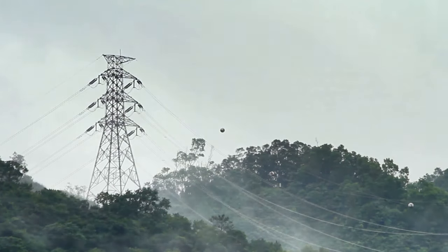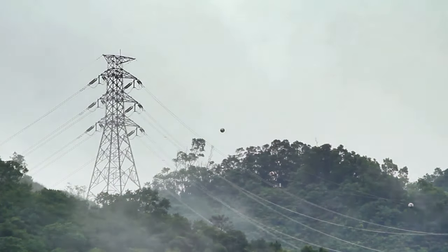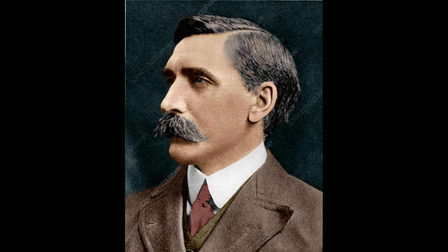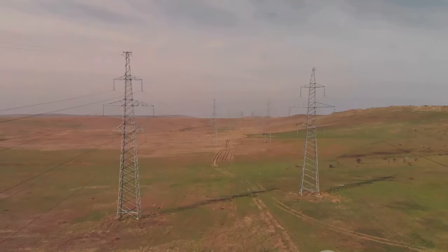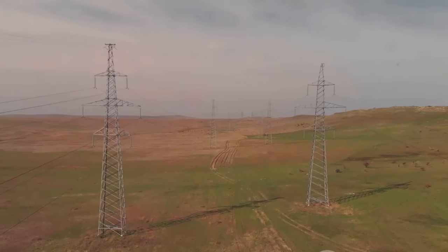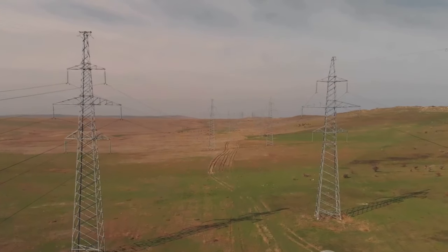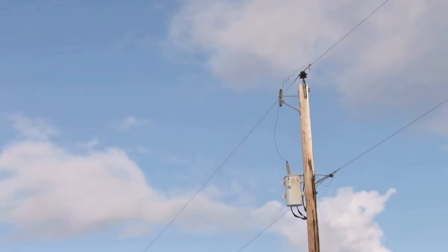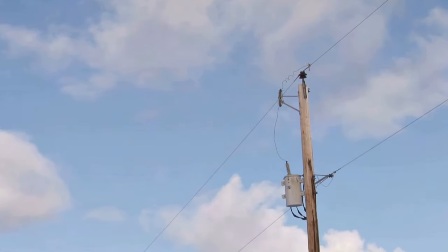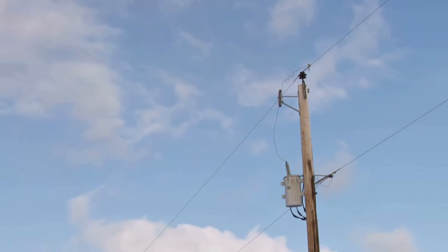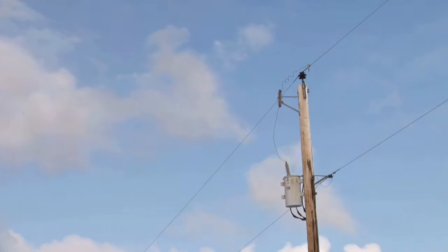This intriguing phenomenon, where the voltage at the receiving end of a long transmission line exceeds the sending voltage under light or no load conditions, has been baffling scientists and engineers since its discovery in 1887. British electrical engineer Sebastian Ziani de Ferranti first noticed this peculiar occurrence when he observed voltage increases at various points in the London power system. This was particularly evident in medium to long transmission cables when the receiving voltage exceeded the sending voltage. Interestingly, this phenomenon doesn't occur in short transmission lines, adding another layer of mystery to the Ferranti effect.